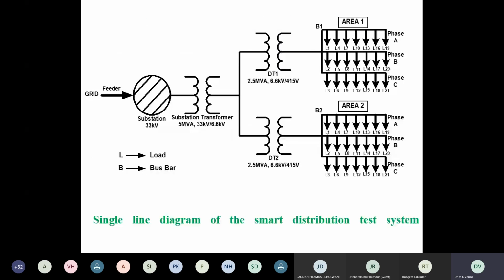He has considered a test system with two areas. Each area has 21 loads connected to it. It's a radial system, and there are two distribution transformers, DT1 and DT2. Here there is a local controller, here there is a local controller, and at the main substation there is the master controller. At each of the loads, we have smart meters. The smart meters send data to the local controller over a bidirectional communication link, and the local controller interacts bidirectionally with the master controller. Whenever there is a shortage of available power, that is detected by the master controller, and based on the load shedding algorithm, it disconnects certain loads in the two areas. Once power comes back to the normal value, the loads are reconnected.